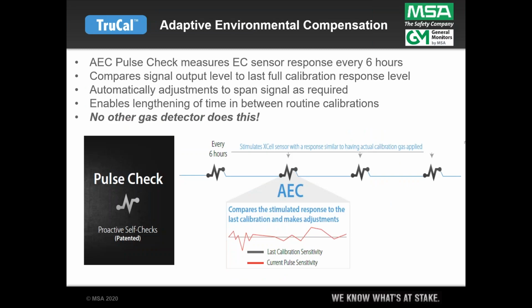The other really neat breakthrough on these sensors is a pulse check. Those little batteries I talked about, little micro fuel cells, create a signal level in response to a microcurrent. The pulse check is a built-in diagnostic that looks at the electric current generated during the calibration process, maps that internally, and is able to recreate that level automatically. Once it has identified the signal level the instrument created during its last full good calibration, every 6 hours the microprocessor stimulates that sensor with the same level of energy that the cell created during cal.